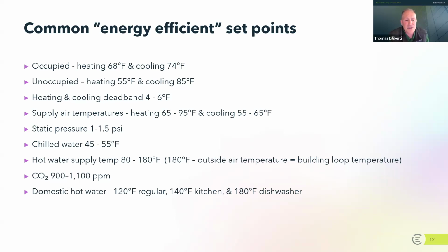And finally, the last set of numbers deal with domestic hot water. This is not the water that's heating the building. This is the water that's being used within the building. Usually for hand washing in bathrooms and locker rooms, that type of thing, you'll see it's 120 degrees Fahrenheit. Water that's supposed to flow into the kitchen for cleaning the dishes and pots and pans is supposed to be set to 140 degrees per the health department. And then finally, the water that's going through the dishwasher is supposed to be set at 180 degrees Fahrenheit. Again, that's in general and what most health departments would advocate for and expect. So just know that those are the common numbers, but I would always check in your region and make sure in your specific area that those are accurate.